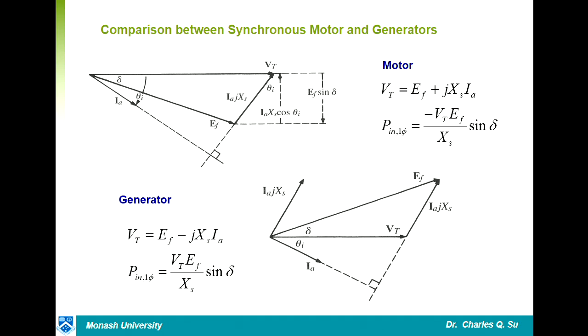Why? Because I have to supply reactive power to your factory, and reactive power has to be supplied through the current, which means I have to increase the current to your manufacturer. If you increase the current, you increase the losses on the transmission line, distribution line, transformers, everything. So the utility says, that's unfair, I have to cover my losses, so I will charge you for reactive power. So in some countries, if manufacturers consume too much reactive power and the power factor drops to 0.5 or 0.6, the manufacturers have to install capacitors.